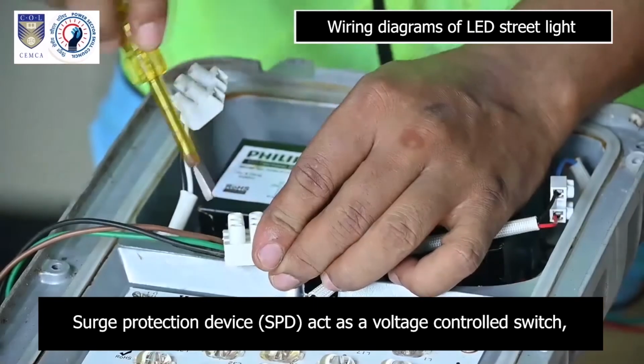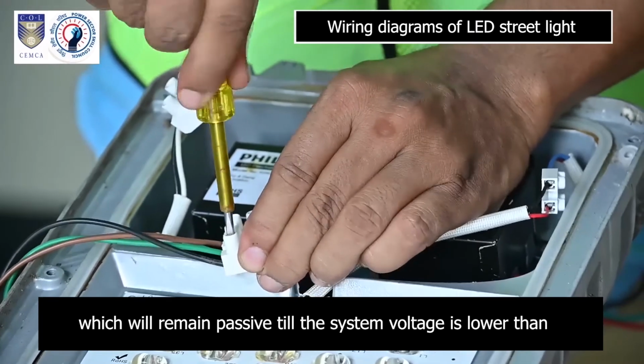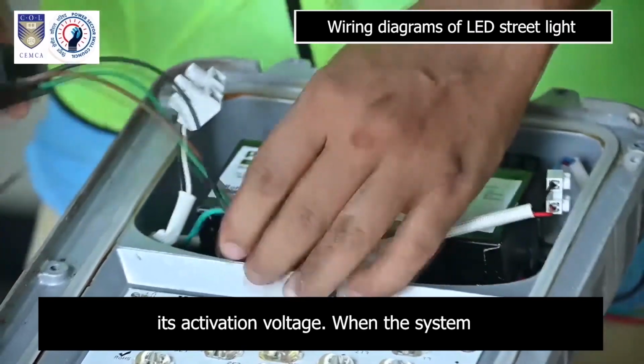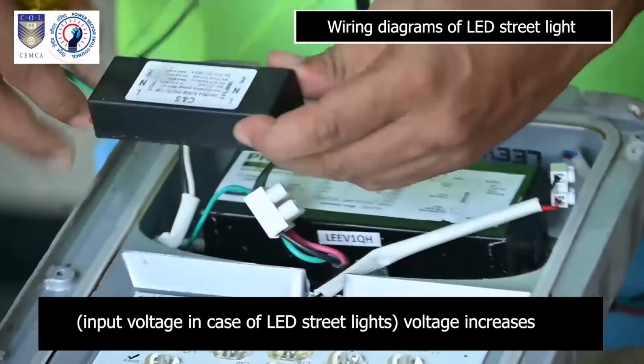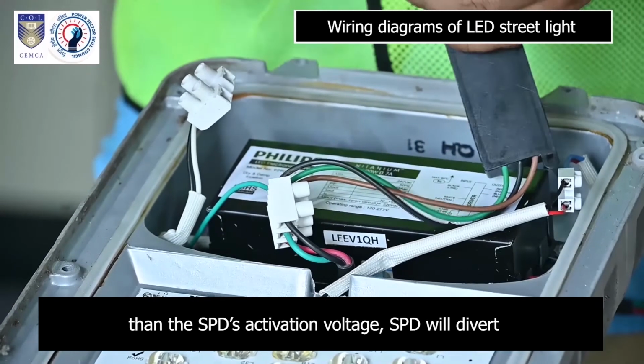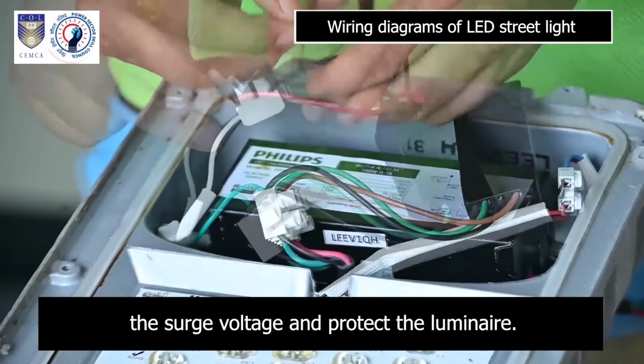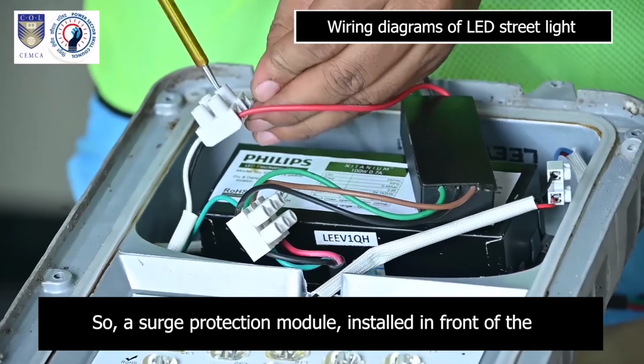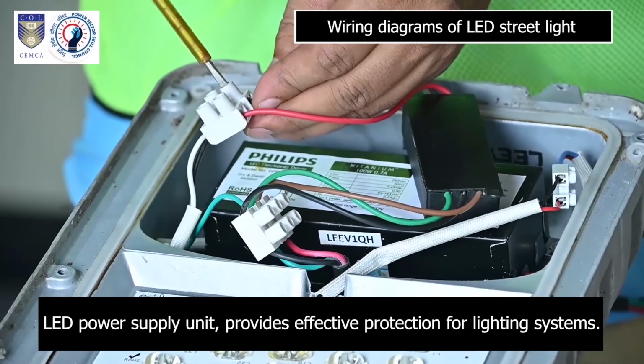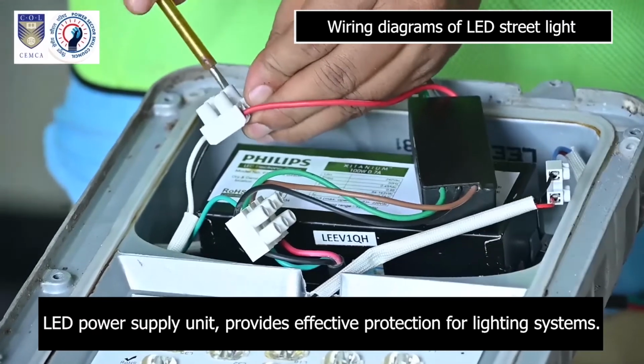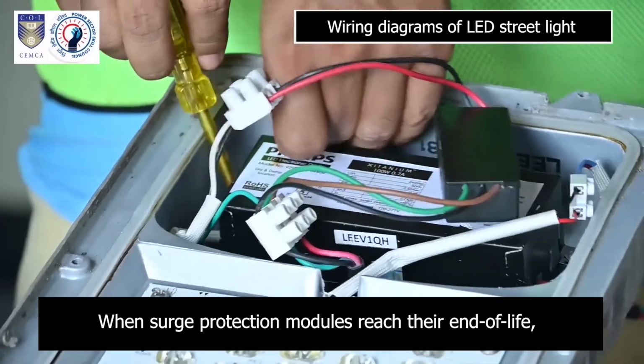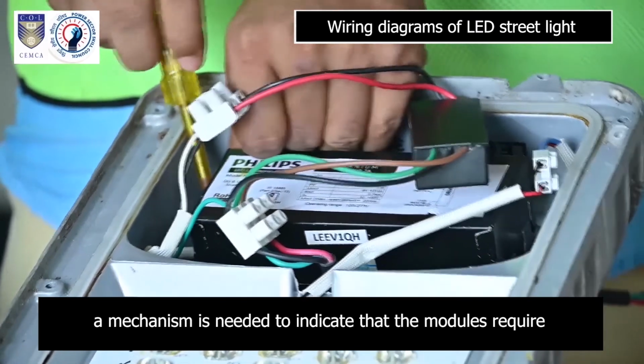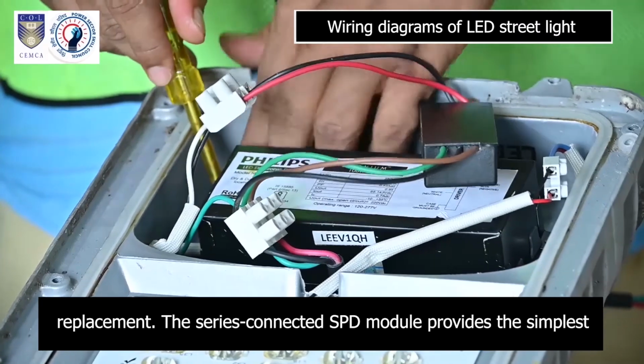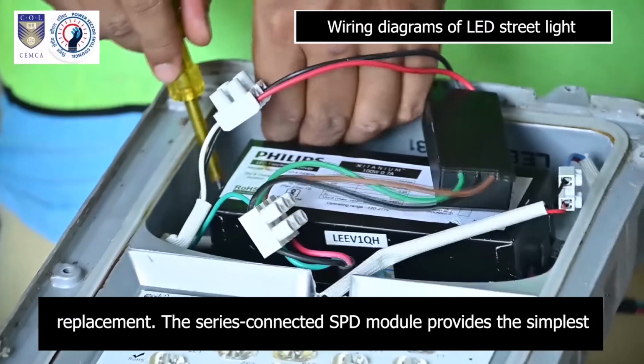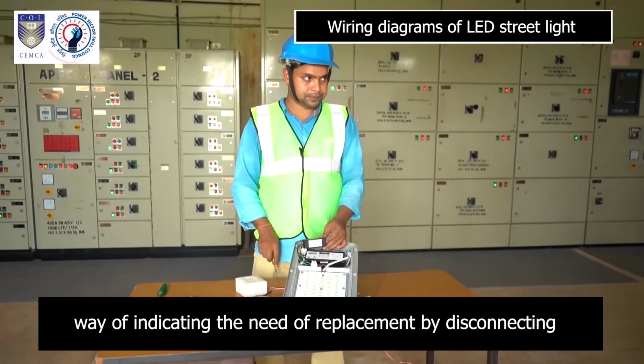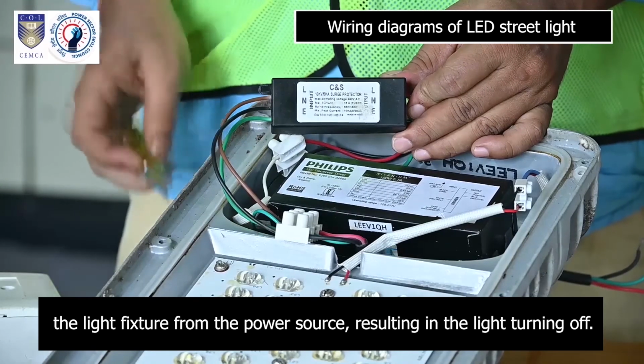Surge protection device SPD acts as a voltage control switch, which will remain passive till the system voltage is lower than its activation voltage. When the system input voltage in case of LED street lights increases more than the SPD's activation voltage, SPD will divert the surge voltage and protect the luminaire. So a surge protection module installed in front of the LED power supply unit provides effective protection for lighting systems. When surge protection modules reach their end of life, a mechanism is needed to indicate that the modules require replacement. The series connected SPD module provides the simplest way of indicating the need of replacement by disconnecting the light fixture from the power source, resulting in the light turning off.